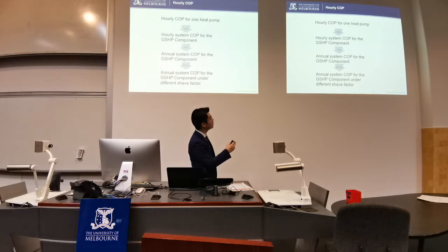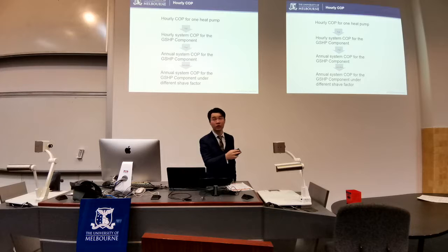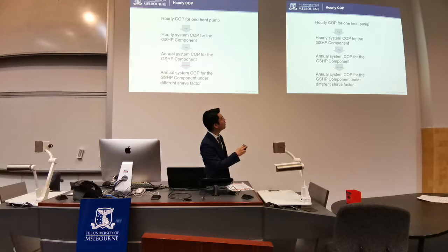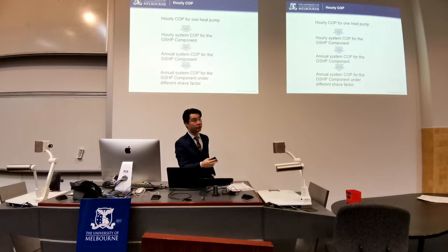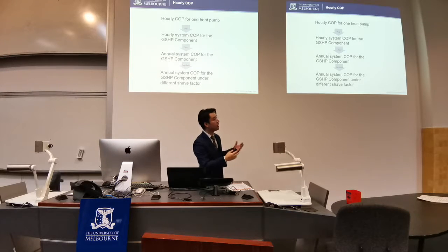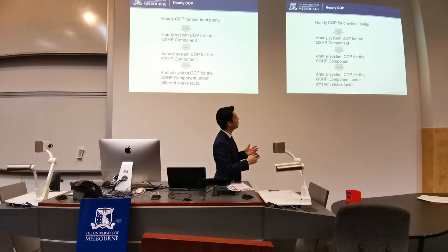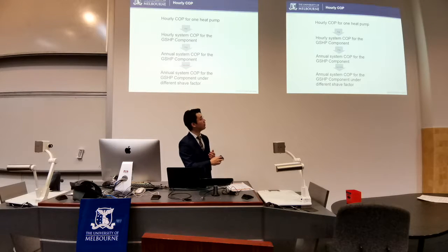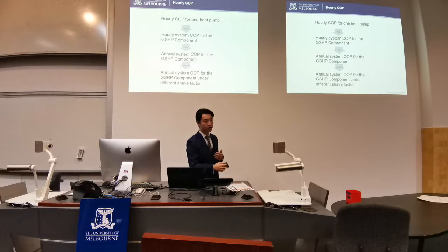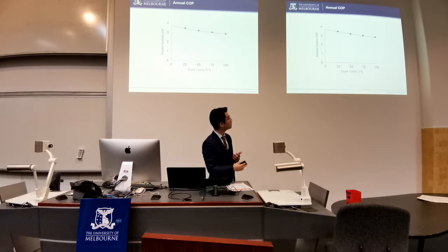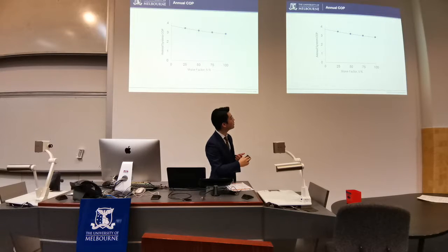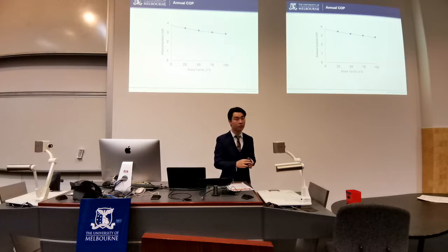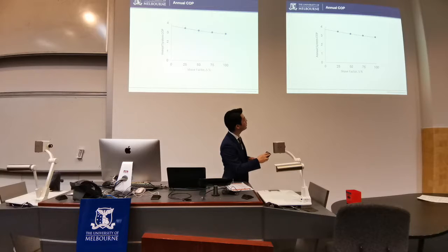So what we have done previously, I just showed you, is that we have the hourly COP for one heat pump, and then we take the average because we have multiple heat pumps in the system. Then we could have the hourly COP for the whole ground source heat pump component within the hybrid system. After doing that, since this is hourly COP, if we do an annual average, we could have the annual average COP for the ground source heat pump component. Then based on this, if we are changing the shave factors, we could have the annual system COP for the ground source heat pump component at different shave factors. And that is the result. Say we have a 25% shave factor, meaning we install about 50 kilowatts of the ground source heat pump system, and then 50%, 75%, and 100%.